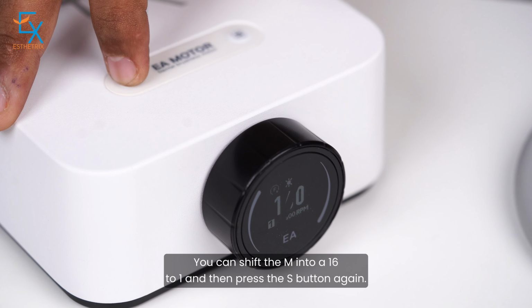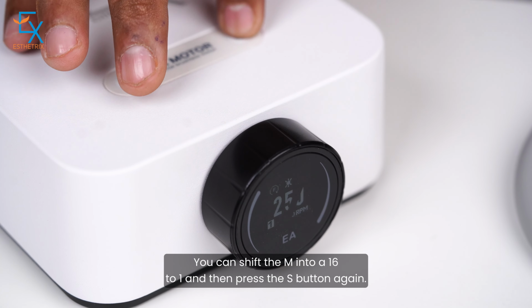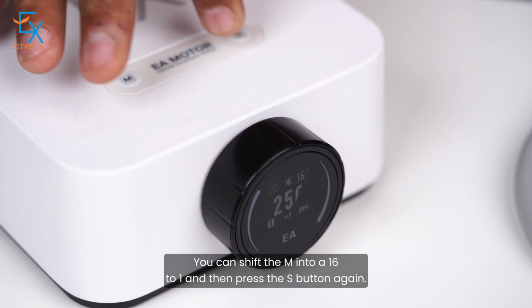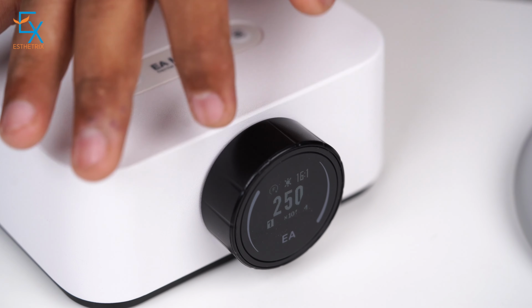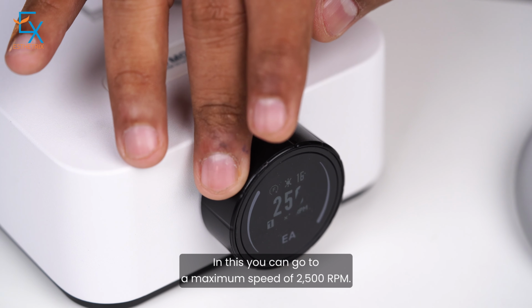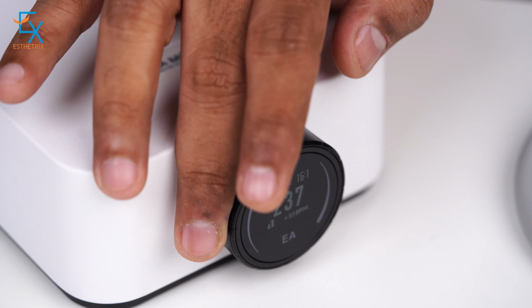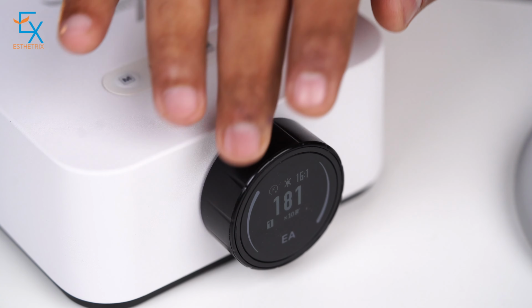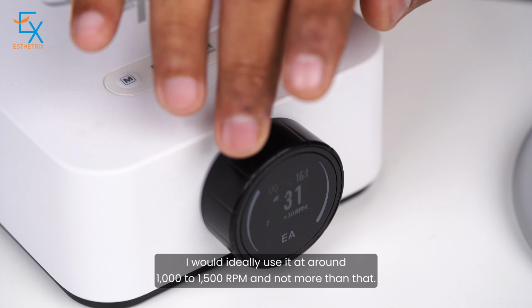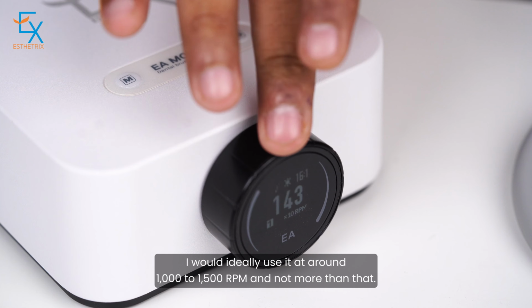You can shift the mode into a 16:1 and then press the S button again. Now the 16:1 is set. In this you can go to a maximum speed of 2500 RPM. That should be decreased further. I would ideally use it at around 1000 to 1500 RPM and not more than that.